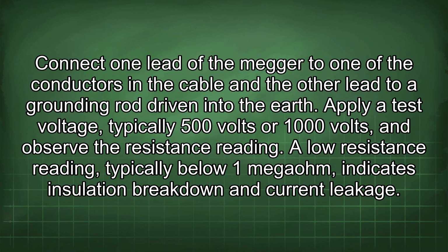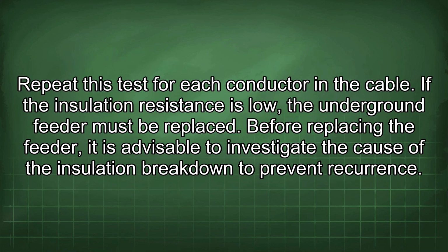Connect one lead of the megger to one of the conductors in the cable and the other lead to a grounding rod driven into the earth. Apply a test voltage, typically 500 volts or 1000 volts, and observe the resistance reading. A low resistance reading, typically below 1 megohm, indicates insulation breakdown and current leakage. Repeat this test for each conductor in the cable. If the insulation resistance is low, the underground feeder must be replaced.